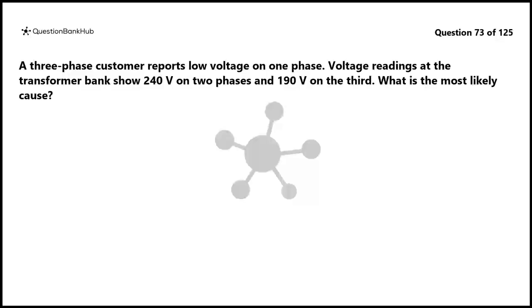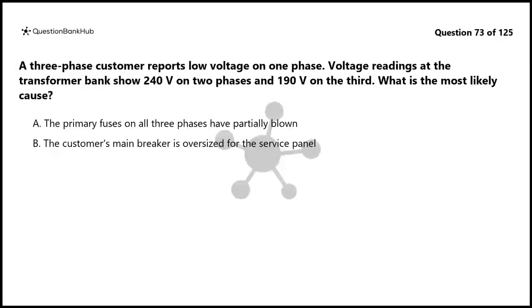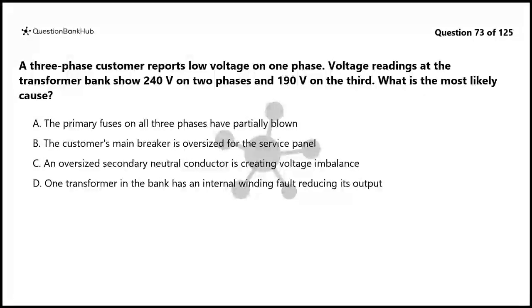Question 73. A three-phase customer reports low voltage on one phase. Voltage readings at the transformer bank show 240 V on two phases and 190 V on the third. What is the most likely cause? A. The primary fuses on all three phases have partially blown. B. The customer's main breaker is oversized for the service panel. C. An oversized secondary neutral conductor is creating voltage imbalance. D. One transformer in the bank has an internal winding fault reducing its output.